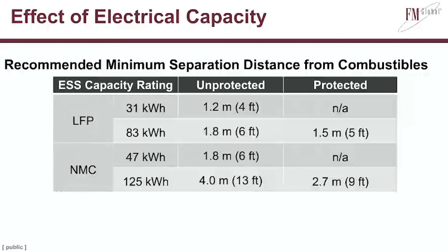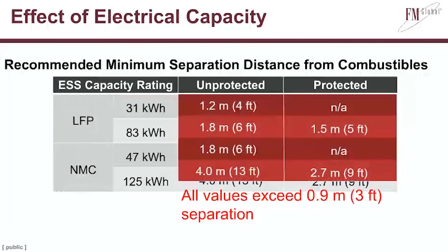And then if you look down, I have the same data for the NMC, and to save everyone the effort of trying to read too much into this table, all of these values exceeded the 3-foot recommendation that you'd see in NFPA 855. Now, mind you, I don't have sprinkler test data for the smaller systems, so we have the information that we have. But I think that this result, at bare minimum, absolutely confirms the need for fire testing. And fire testing around that 50 kilowatt hour criteria that NFPA 855 has seems to make sense because the larger systems have separation distances that exceed what the code thinks is reasonable.